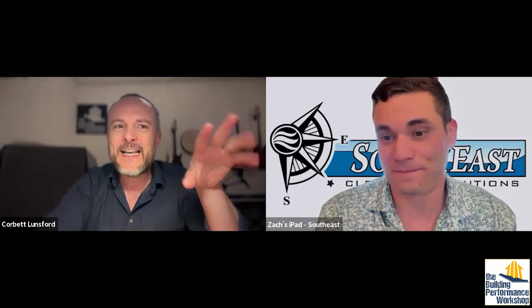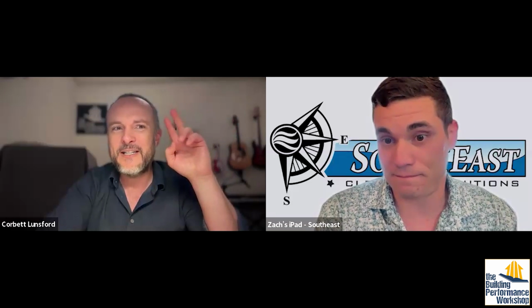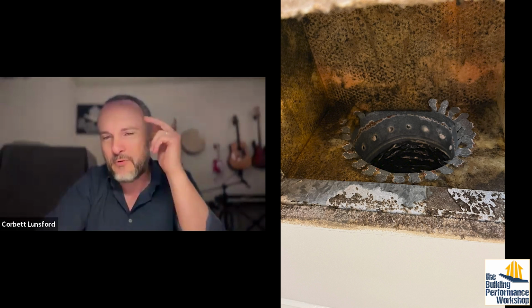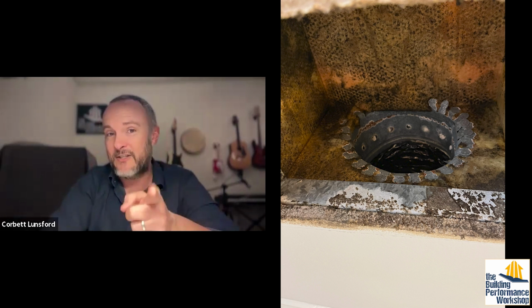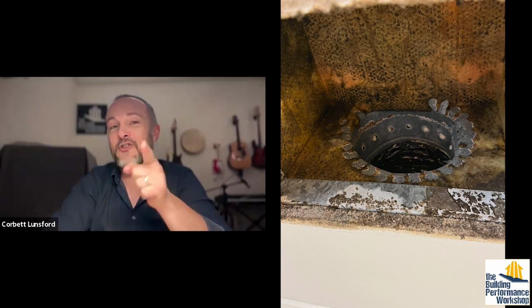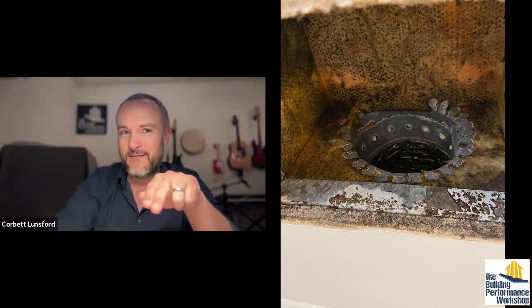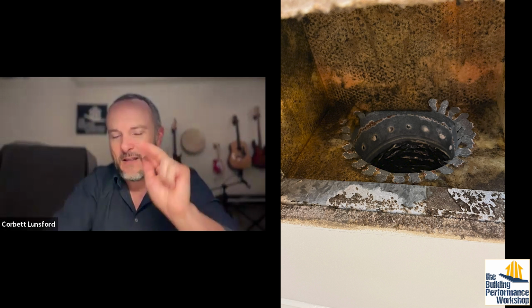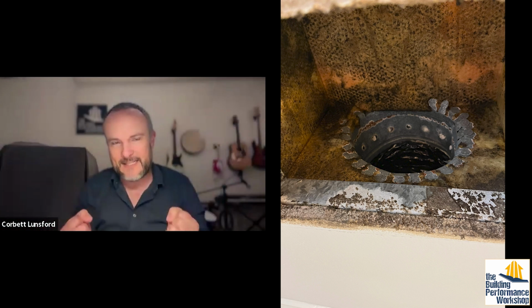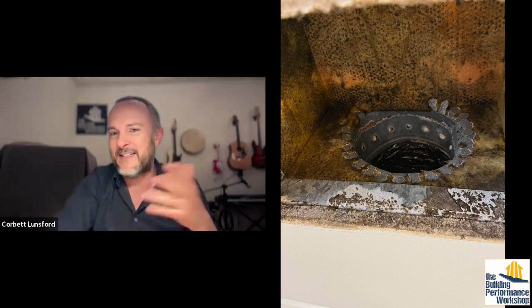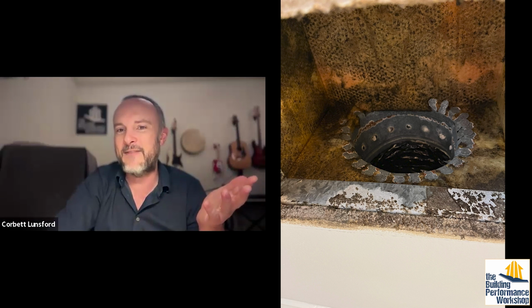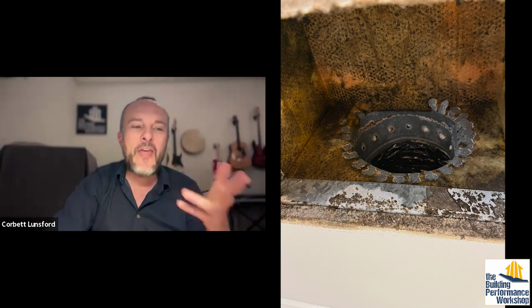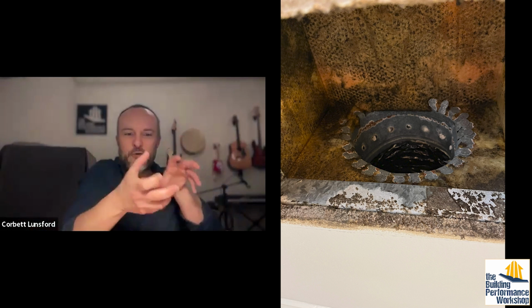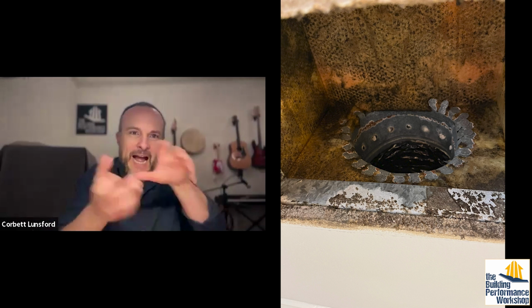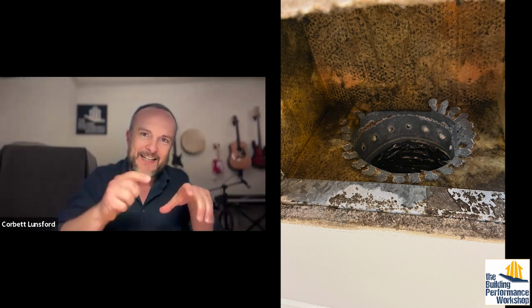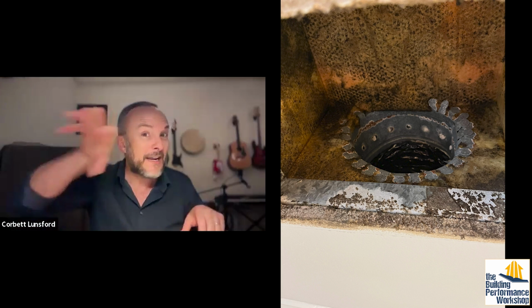Yeah, this gets at the other thing, which is problematic, which is if we have this boot, for example, and we're going to get to in a second, Zach has an idea for how to potentially encapsulate this thing, which I want to have him tell you about. But in the meantime, if we can just take this thing out because it's that contaminated, we're not even going to worry about trying to save this thing. Let's get it out of there. Then when you pull it out, if it's not taut, I can pull the flex duct and disconnect the flex duct and let it go back into the ceiling where I can still reach it.